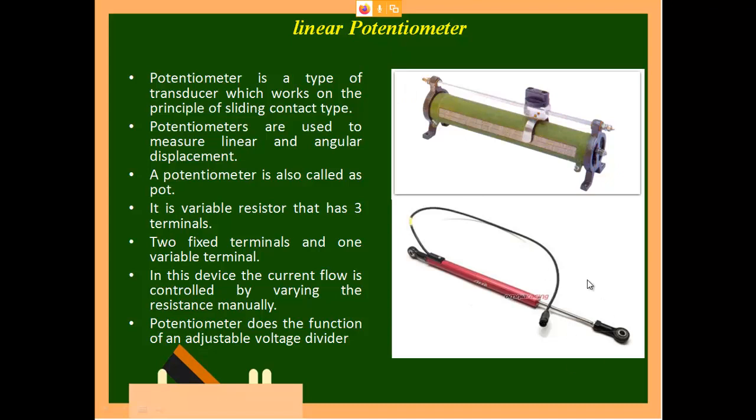Okay, this one has a hydraulic inside, and this hydraulic will try to move. If that hydraulic is moving, obviously I will have a rod arrangement, and inside this rod I have a conductor. So if this is moving, automatically you will get an output. Okay, so when there is a movement, that is identified and given. The movement of this valve arrangement is not done by me, and that movement is read by the sensor with the principle of potentiometer. Okay, so the potentiometer concept is being used to identify the displacement taking place.